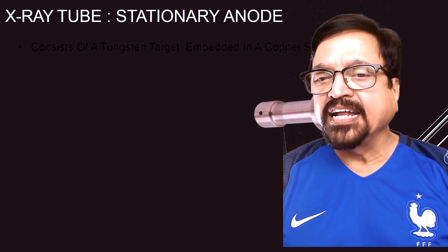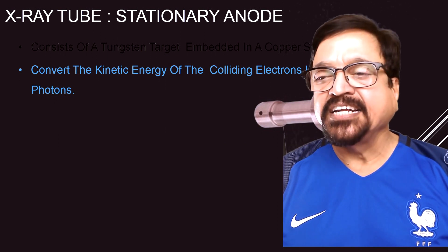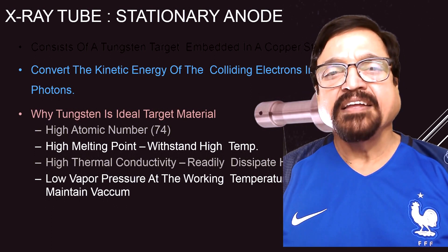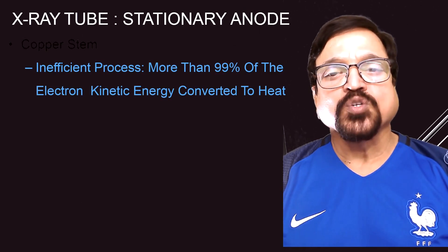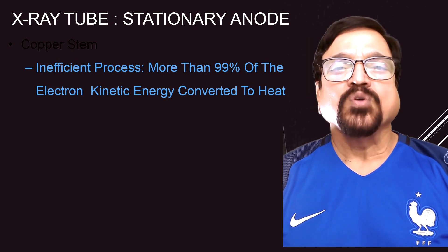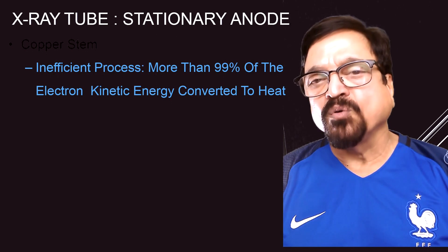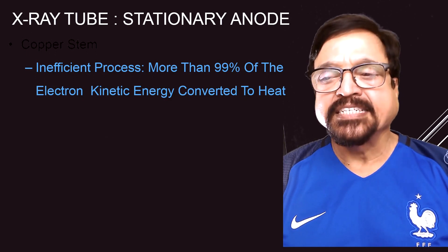You can see on the outside the copper and inside the tungsten. The role of this combination is to convert kinetic energy into X-ray photons. Now regarding heat — more than 99 percent of the energy created here is in the form of heat, so heat is the main problem. Only about one percent is X-rays, which travel to the patient or the area to be examined. That is why the main challenge is the production of heat and its dissipation.